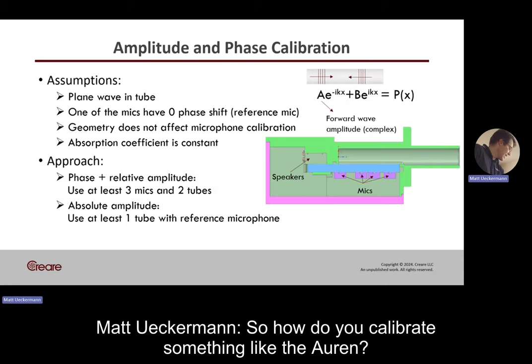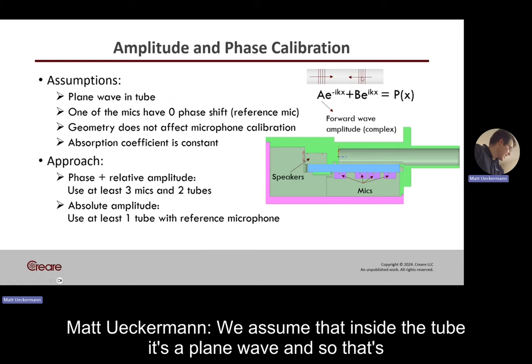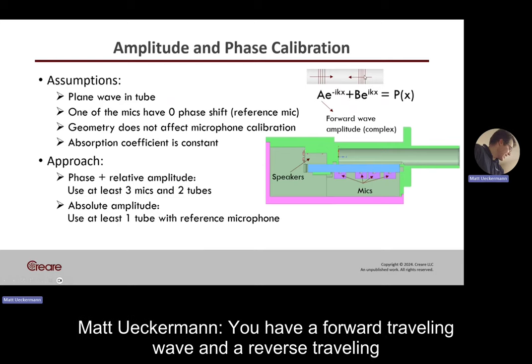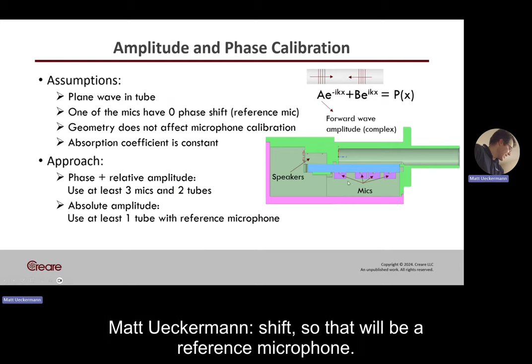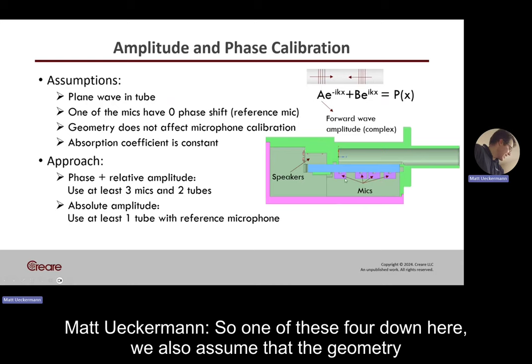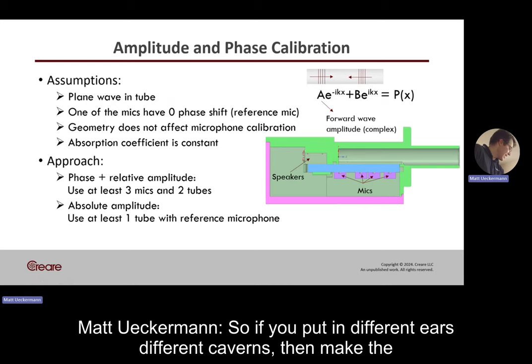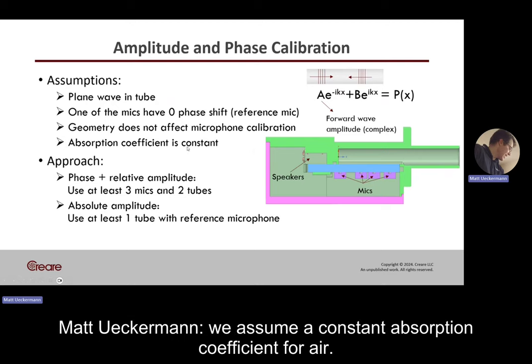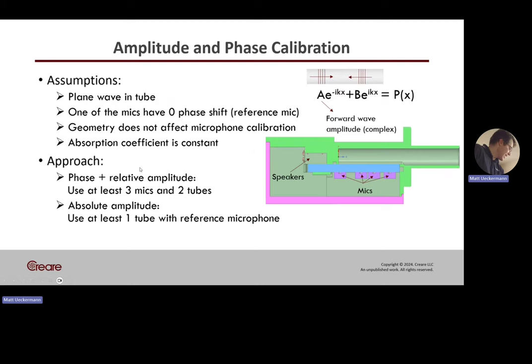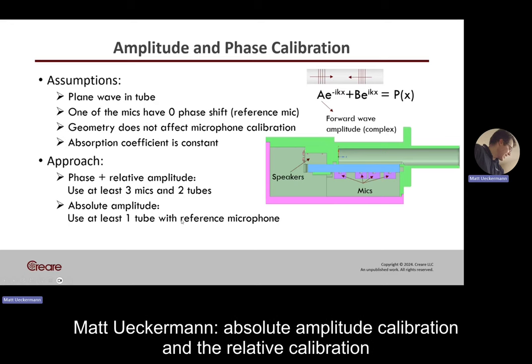How do you calibrate something like the Auren? We start with a plane wave assumption — we assume that inside the tube it's a plane wave, with a forward-traveling wave and a reverse-traveling wave. One of the microphones has a zero-phase shift, serving as the reference microphone. We also assume that the geometry doesn't affect the mic phase and amplitude calibration across different ears and cavities, and we assume a constant absorption coefficient for air. It's a two-step approach: first a relative calibration, then an absolute amplitude calibration.